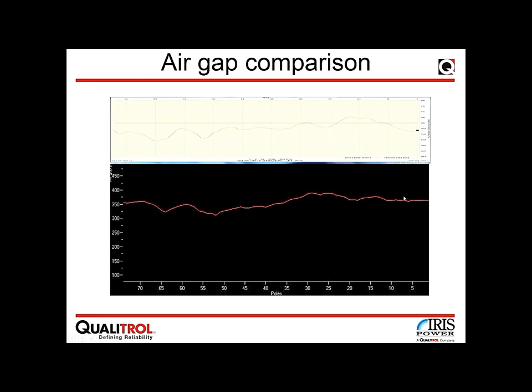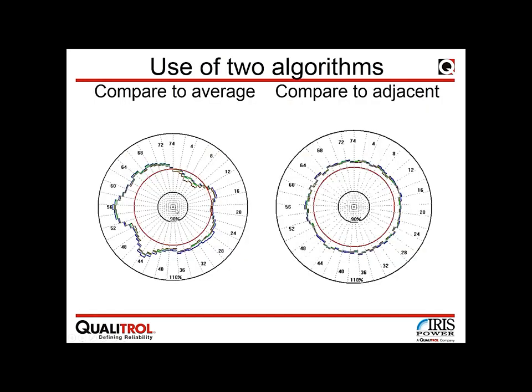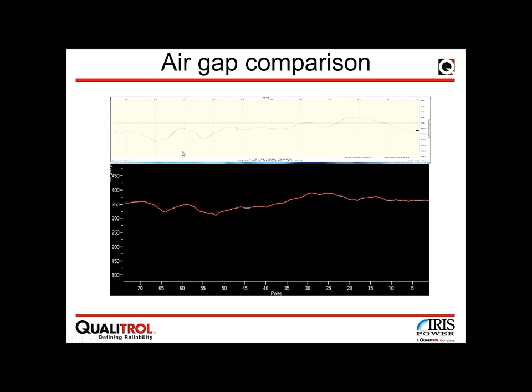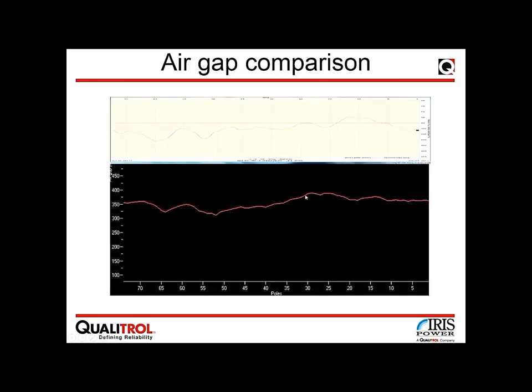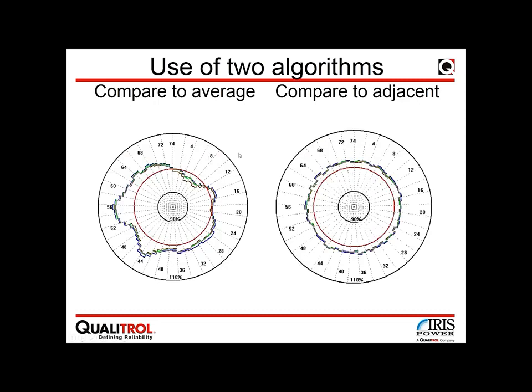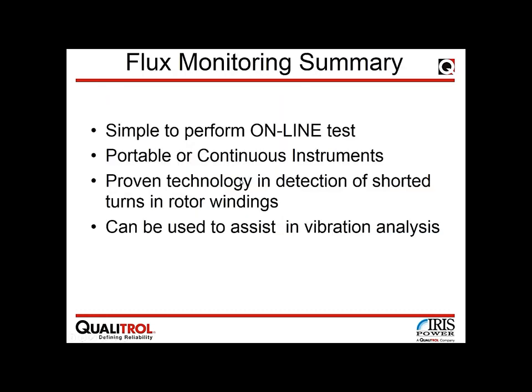The air gap monitoring signal confirms rotor shape findings. An oval rotor with non-uniform air gap does not prevent data collection or detection of shorted turns — a pole with shorted turns will show visibly lower output than other poles. This is an online method, relatively simple to collect data with portable or continuous instruments. The main role is assisting in vibration analysis; a rotor short turn is not good news but is not catastrophic for machine operation.